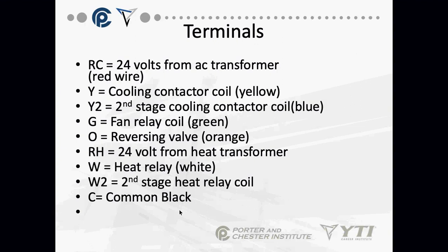So we have terminal designations. RC is 24 volts from the cooling transformer, in case you have a different transformer for heating. Most of the time now they're the same. Y is our cooling contactor. That controls our outdoor unit. On some systems, the more efficient you get, Y2 is second stage cooling. It might have a blue wire under it, might have another type of wire.